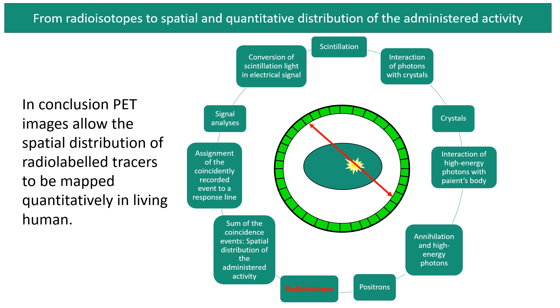From radioisotopes to the spatial and quantitative distribution of the administered activity, many steps are performed sequentially. PET is based on the use of radioisotopes that emit positrons. Through annihilation, the positron energy and mass together with the mass of an atomic electron is converted into the energy of two photons, each with an energy of 511 keV. The two photons may or may not interact with the patient body before impacting on crystals. Interaction with the crystals produces scintillation light that is converted into electrical signals. Only coincidence events are used, and to each coincidence event a line of response is assigned. Finally, the sum of events leads to a spatial distribution of the administered activity in the patient body.